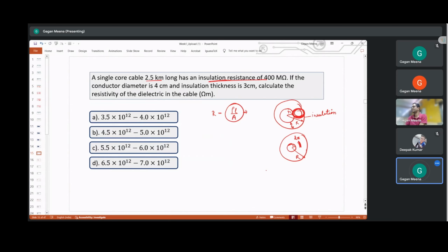So here we know capital R and the insulation resistance is 400 mega ohms. We have to find resistivity. We have 2 pi, and length we know is 2.5 kilometers, so we convert it into meters since resistivity is in ohm meter - we have to divide by meter to convert into ohms, because R by r is dimensionless.